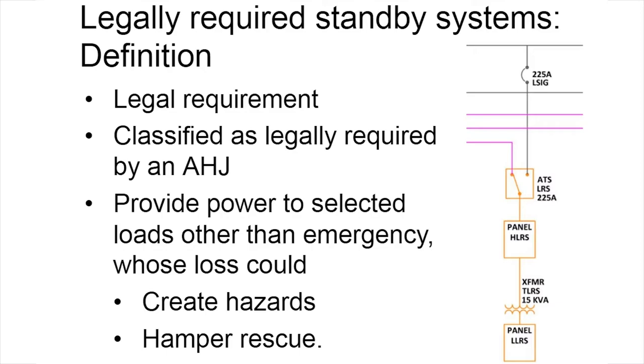Next in the Big Three hierarchy of standby systems is legally required standby, and that's described in Article 701. Here's the expanded diagram of the legally required standby system on the right, showing the normal feed, transfer switch, and a couple of levels of distribution. Legally required standby systems are, as their name says, legally required, and specifically classed as legally required systems by law, codes, or an AHJ. They power loads whose loss could create some sort of hazard or hamper rescue efforts, but wouldn't threaten human life directly. Some examples might be smoke removal systems, particularly from atriums, sewage disposal systems, and some specific heating and cooling systems.